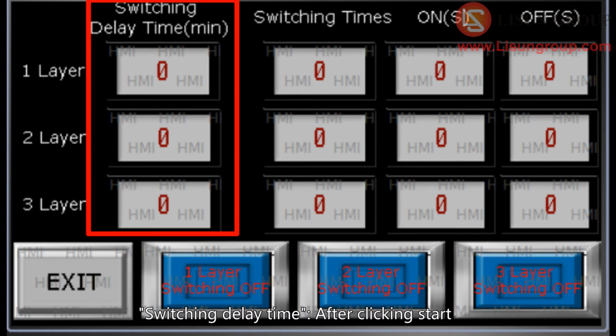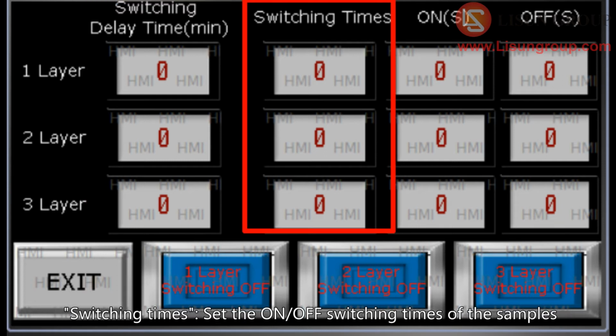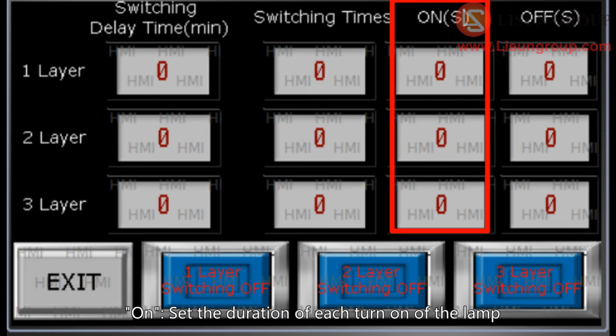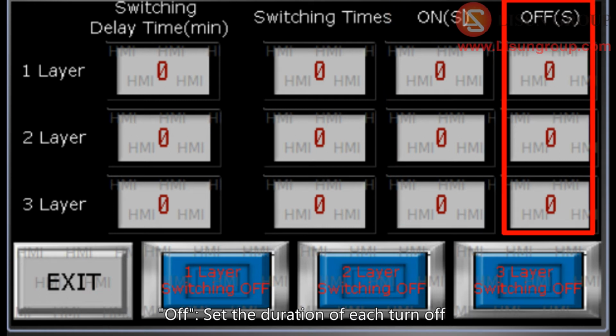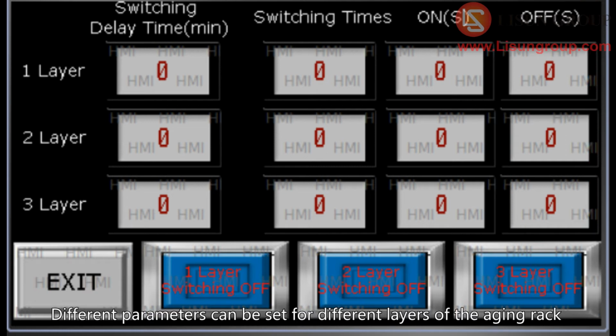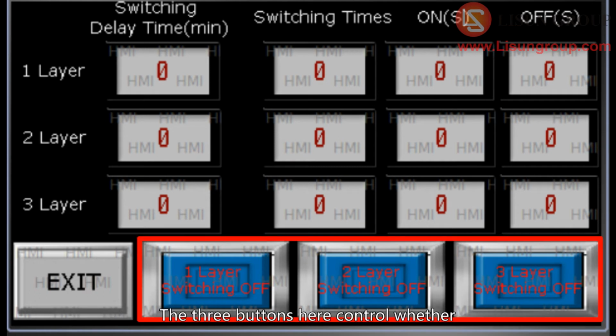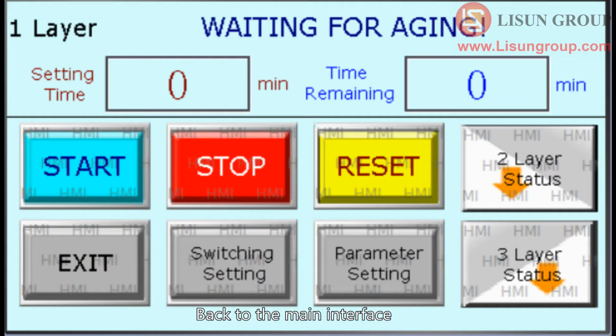Switching delay time. After clicking Start, the formal switch aging test will not start until the delay time is finished. Switching times. Set the on-off switching times of the samples. On. Set the duration of each turn on of the lamp. Off. Set the duration of each turn off. Different parameters can be set for different layers of the aging rack. The 3 buttons here control whether the 3 layers of the rack participate in the aging test. Back to the main interface.